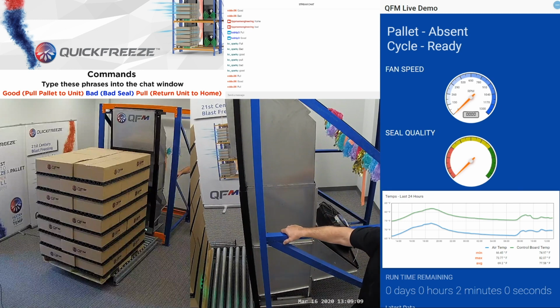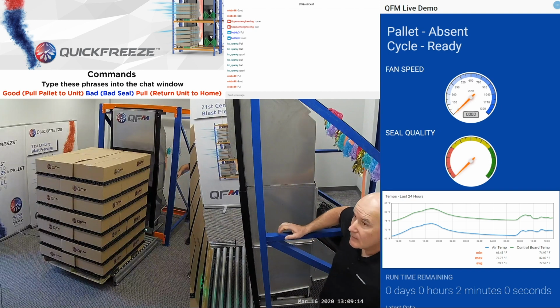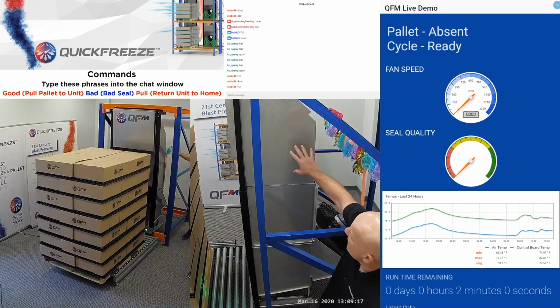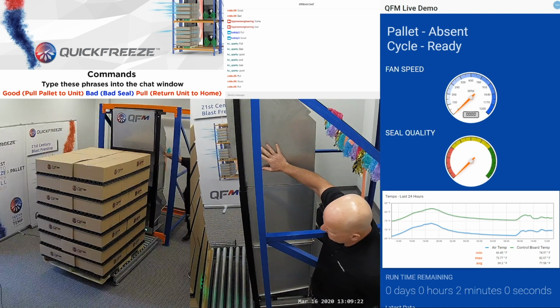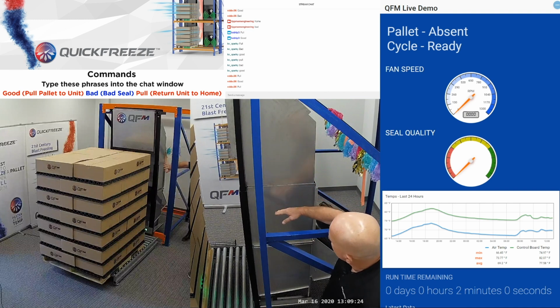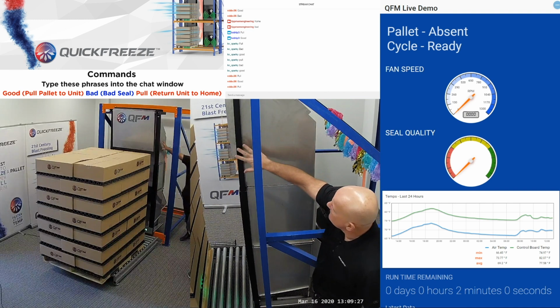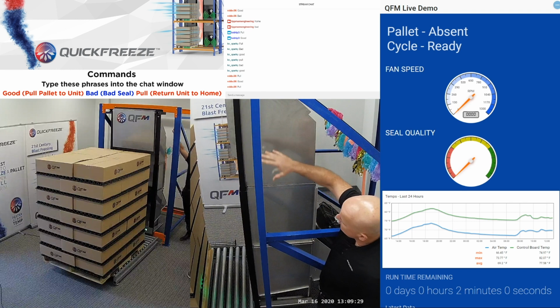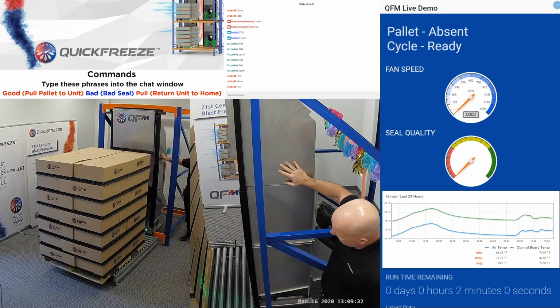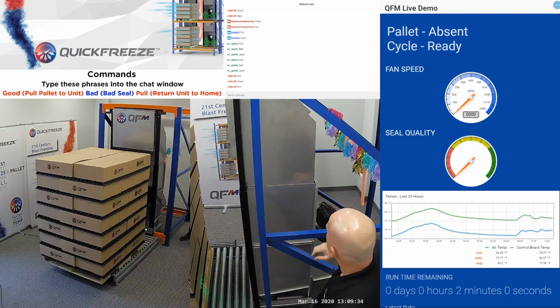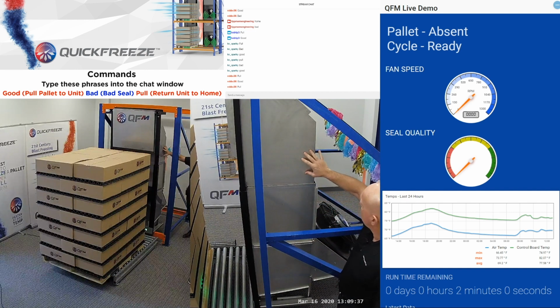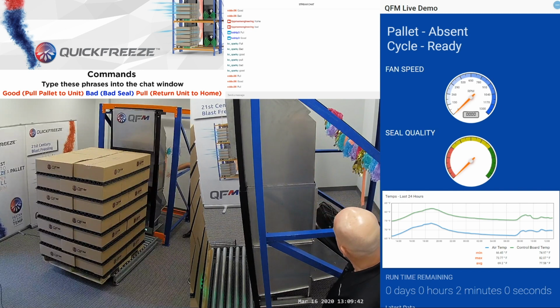Now, I'd like Dan, if you could give us just a kind of an overview of what we're seeing here. Sure. At least this one camera angle has a pretty good view of the side of the unit. This is a standalone pallet freezing system. It consists of a telescoping member, so this portion telescopes to accommodate a whole range of rack opening heights. And this sheet metal area is called the reduced pressure plenum. And on the back side is a direct drive axial fan.